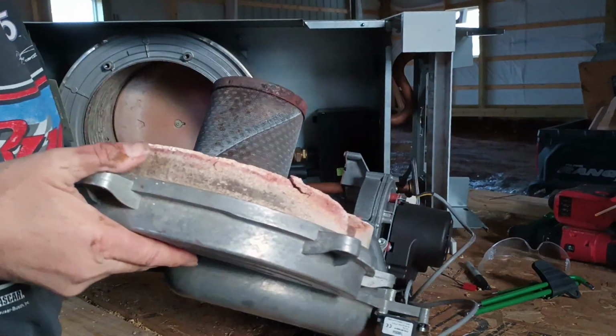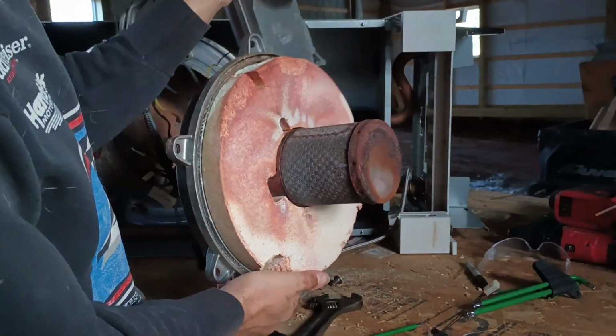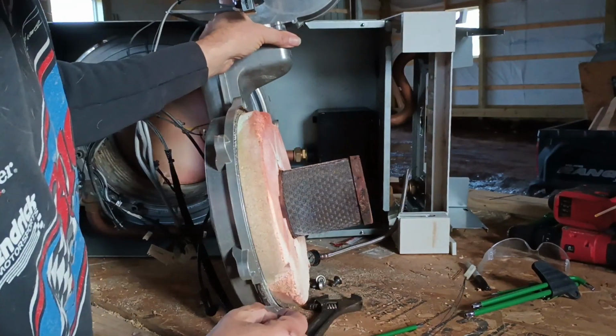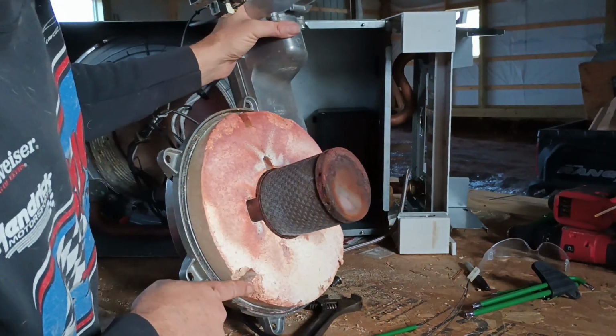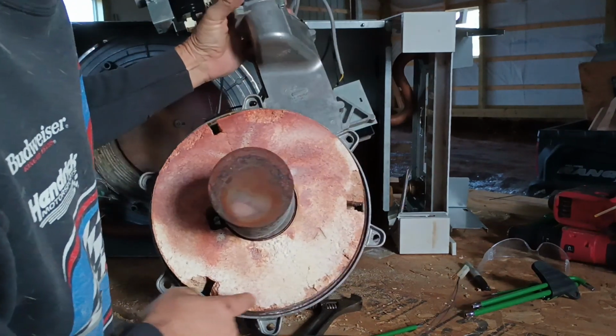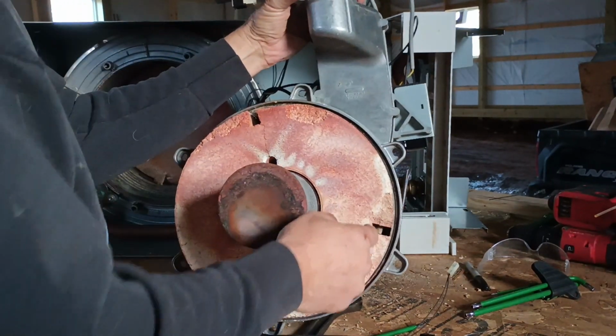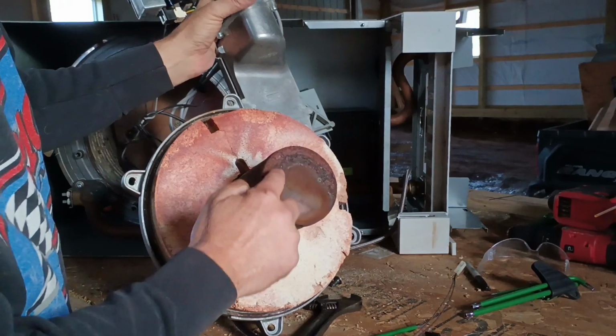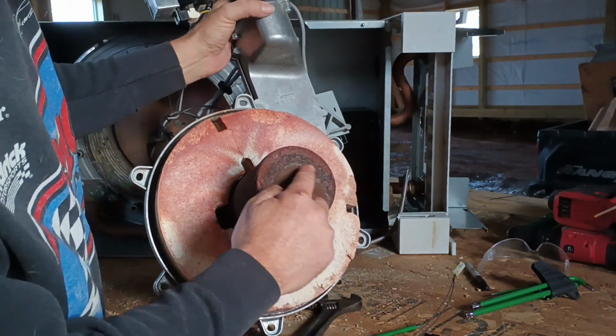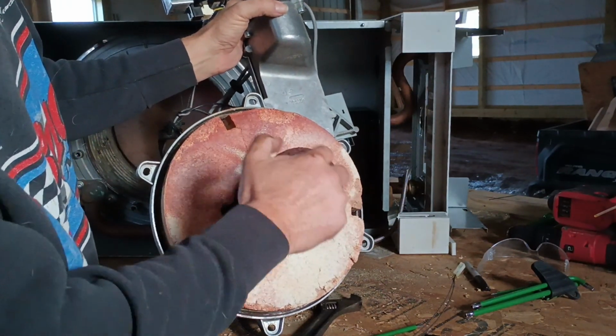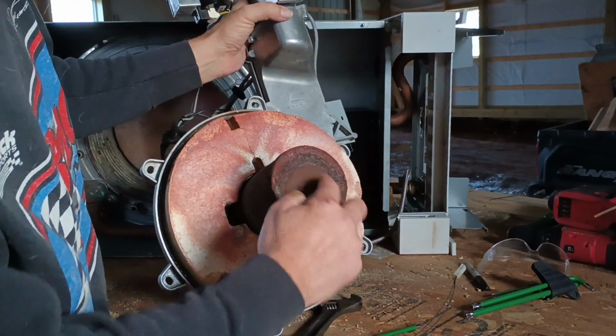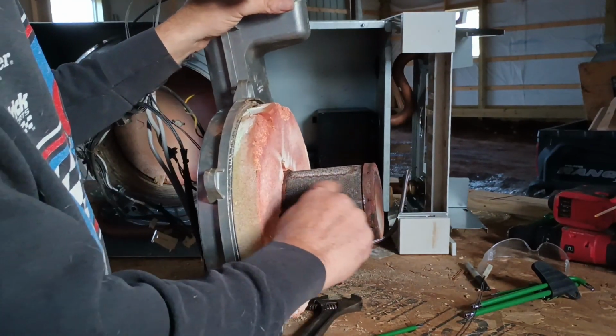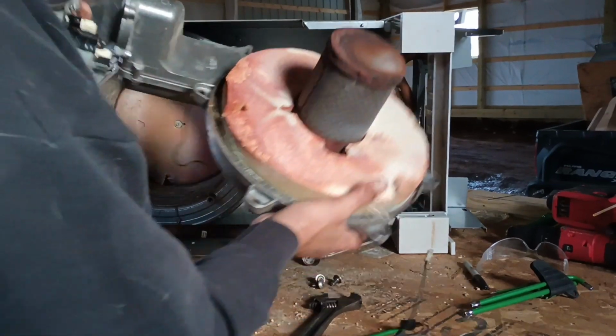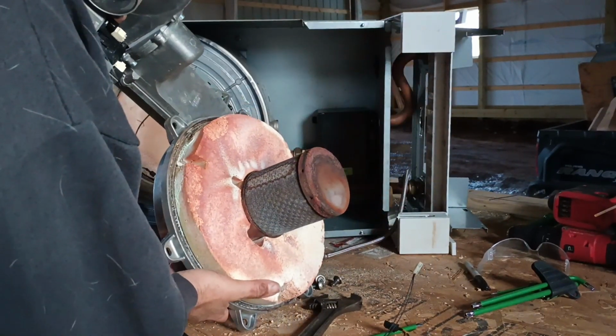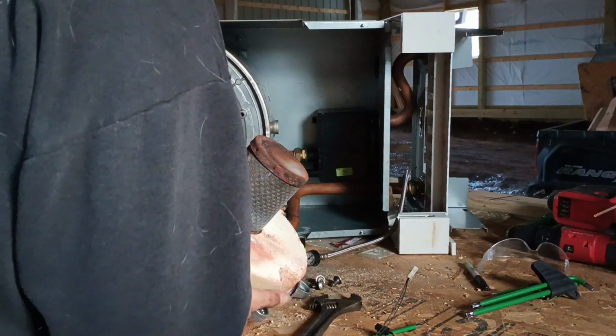And so here is the inside of the combustion chamber, or the burner assembly anyway. First look, it looks like we're missing a little refractory in a couple of spots. The burner itself, these signs you can see here, this is going to be the bottom of that burner. You get this with excessive condensation. So this boiler has definitely been abused, hasn't been well taken care of. Set this off to the side.